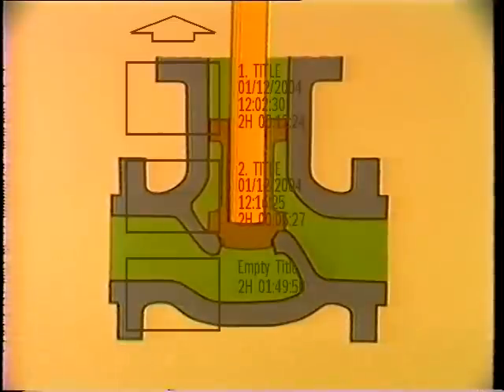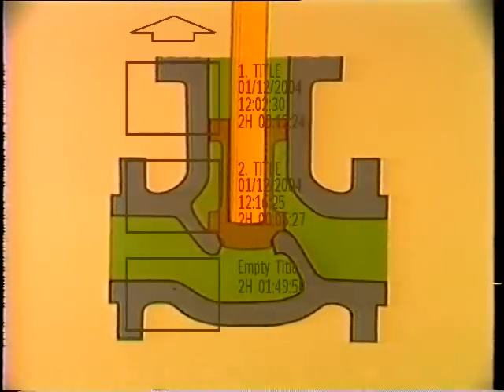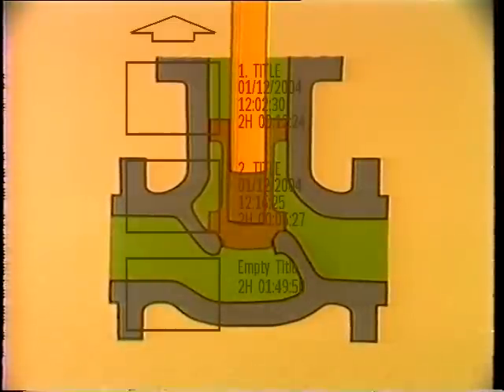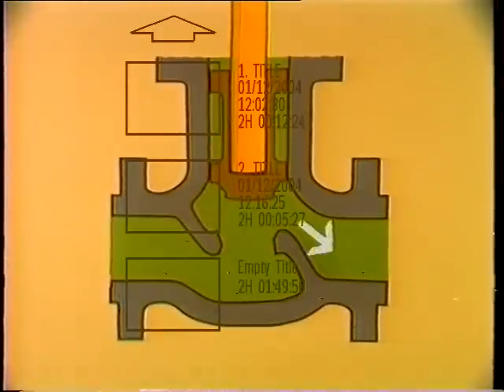The third type of check valve, the stop check, is like a modified globe valve. When the stem is completely down the valve is closed, but when the stem is raised the disc operates like the disc on a lift check valve — it responds to system pressure. As system pressure increases to overcome the weight of the disc, it is lifted and flow can be carried through the valve. This type of valve is common to the boiler feed isolation valve.